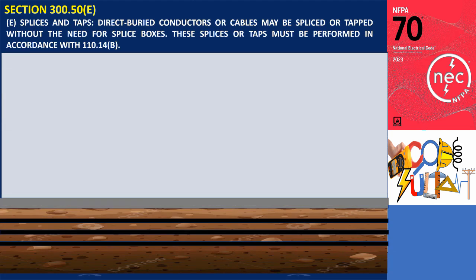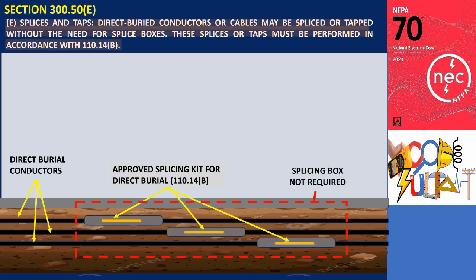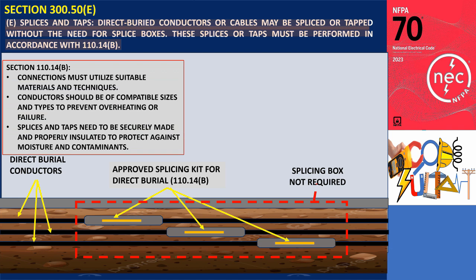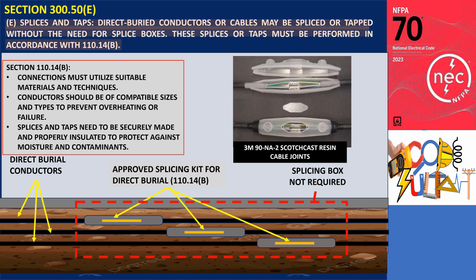Section 300.50(E), Splices and Taps: direct buried conductors or cables may be spliced or tapped without the need for splice boxes. These splices or taps must be performed in accordance with 110.14(B), which outlines the correct methods for making electrical connections, emphasizing that connections must utilize suitable materials and techniques, conductors should be of compatible sizes and types to prevent overheating or failure, and splices and taps need to be securely made and properly insulated to protect against moisture and contaminants. The accompanying photo illustrates an approved splicing kit — specifically the 3M 90NA2 Scotchcast resin cable joints — designed for straight joints, splicing, or connecting multi-core non-shielded polymeric cables with XLPE insulation and core conductors ranging from 16 mm² to 25 mm².